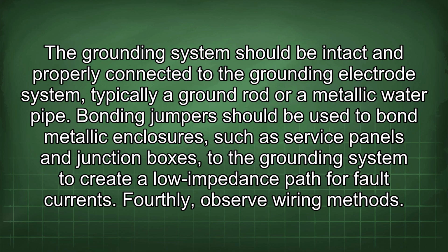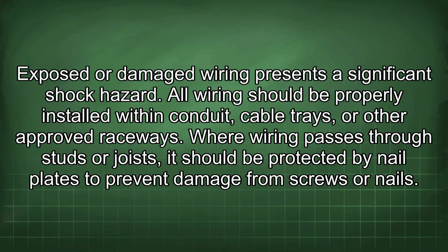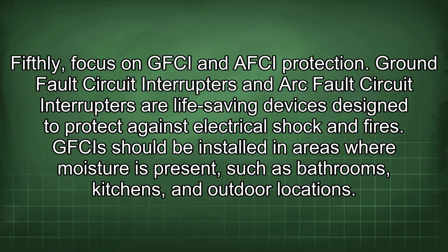Fourthly, observe wiring methods. Exposed or damaged wiring presents a significant shock hazard. All wiring should be properly installed within conduit, cable trays, or other approved raceways. Where wiring passes through studs or joists, it should be protected by nail plates to prevent damage from screws or nails.